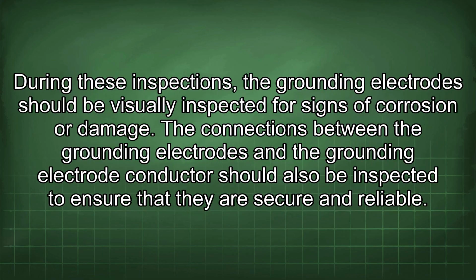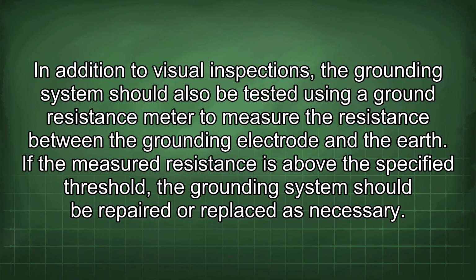During these inspections, the grounding electrodes should be visually inspected for signs of corrosion or damage. The connections between the grounding electrodes and the grounding electrode conductor should also be inspected to ensure that they are secure and reliable. In addition to visual inspections, the grounding system should also be tested using a ground resistance meter to measure the resistance between the grounding electrode and the earth. If the measured resistance is above the specified threshold, the grounding system should be repaired or replaced as necessary.